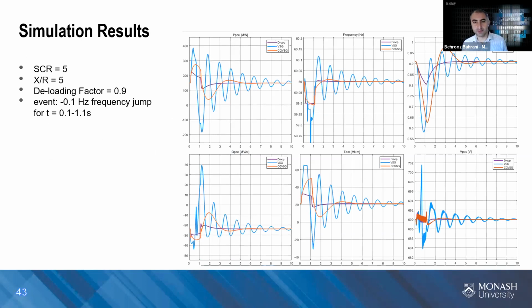Particularly, I would like to talk a little bit about VSG and CG VSG. Droop will not give you the inertia that you would require. The test conditions here: SCR 5, X/R ratio 5, and the deloading factor, meaning that we have deloaded the wind farm in order to give us headroom to operate. And then the event that you're looking at here is a frequency jump, so a 0.1 hertz frequency jump, and we are looking at the performance of these different controllers.